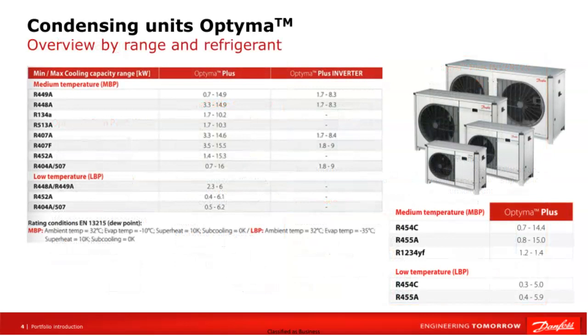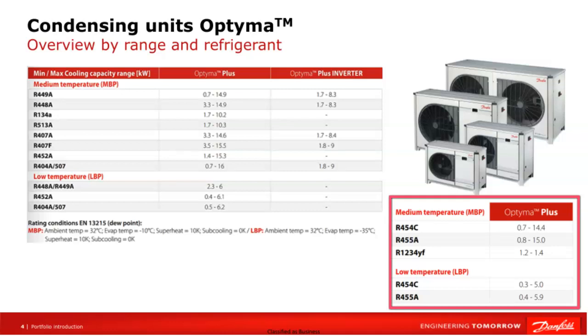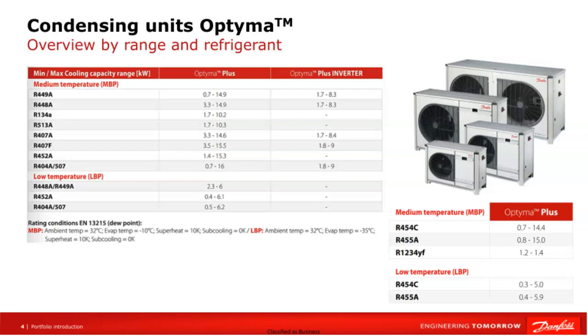On this slide, we present a summary containing key information about the capacity ranges of Optyma Plus condensing units and Optyma Plus inverter units, depending on the refrigerant used. Analyzing this data is extremely important because it helps understand the cooling capacity of individual condensing unit family. The list shows that the Optyma Plus inverter units are only available in a medium temperature version, and there are no versions available working with ultra low GWP refrigerants such as R454C or R455A. In addition, we note that the Optyma Plus family of units has a wider cooling capacity range.